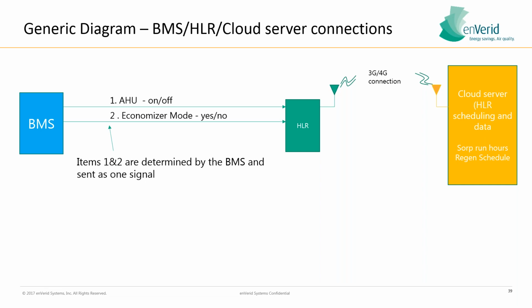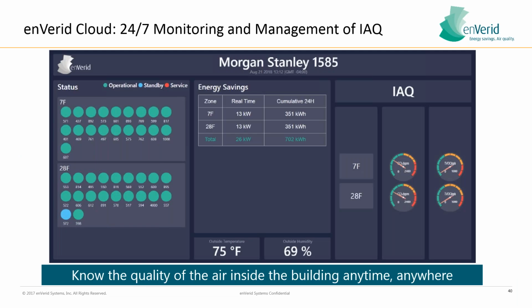Data surrounding indoor air quality and unit status can be broadcast by 3G, 4G wireless connection. Antennas on the side of the unit. And here's actually a snapshot of an installation that Odell went and visited, the Morgan Stanley building, their worldwide headquarters in Times Square, New York, where we show unit status, we model in energy savings, and we show CO2 and total VOCs readouts from the sensors in the units and in the space as well.